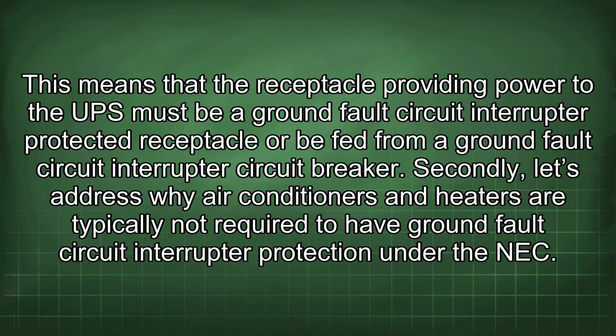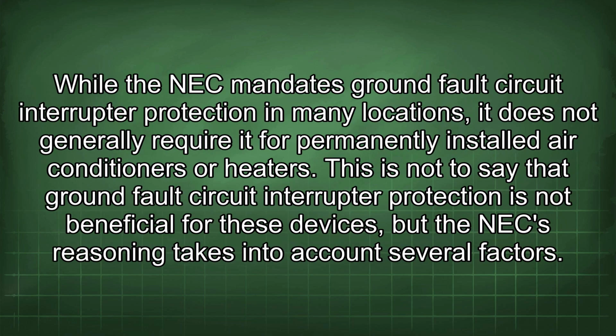Secondly, let's address why air conditioners and heaters are typically not required to have ground fault circuit interrupter protection under the NEC. While the NEC mandates ground fault circuit interrupter protection in many locations, it does not generally require it for permanently installed air conditioners or heaters. This is not to say that ground fault circuit interrupter protection is not beneficial for these devices, but the NEC reasoning takes into account several factors.